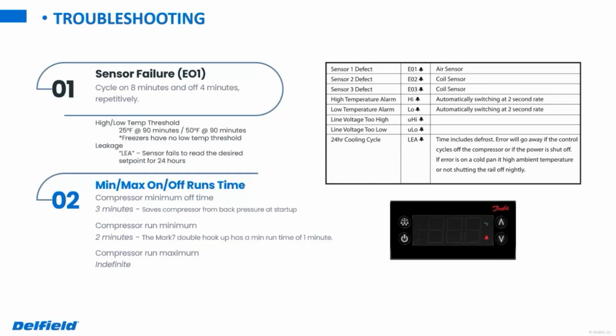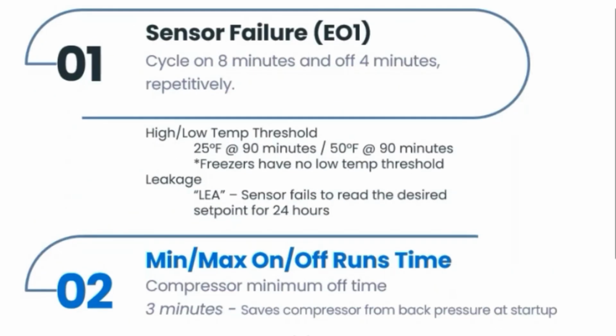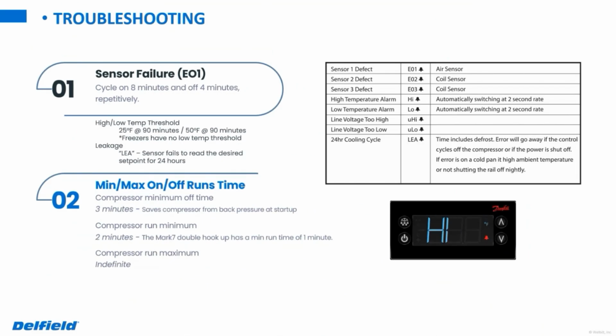We have the different high and low temperature alarms. The thresholds for those are listed there on the left-hand side. One thing too, as far as that E01 sensor failure, these will actually operate in what I would consider a safe mode. If we have an air probe failure, it'll cycle the condensing unit 8 minutes on, 4 minutes off, continuously until that probe is replaced.